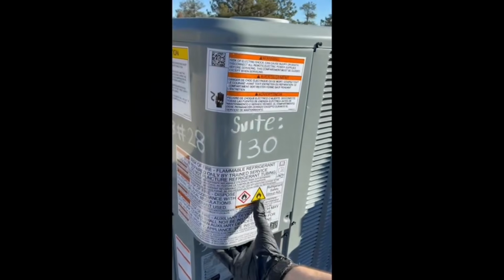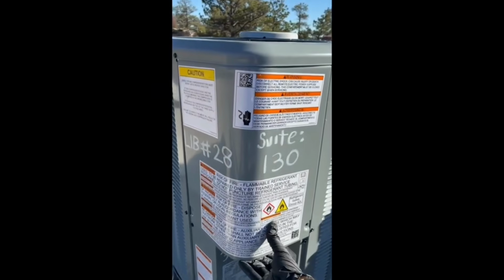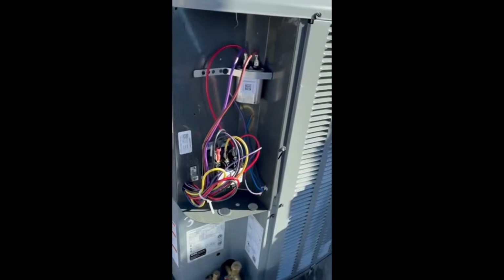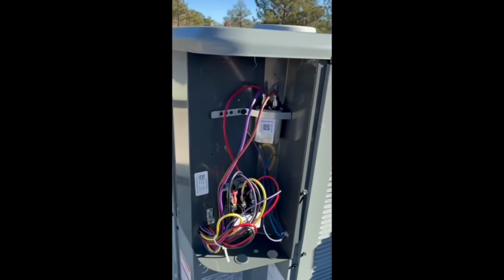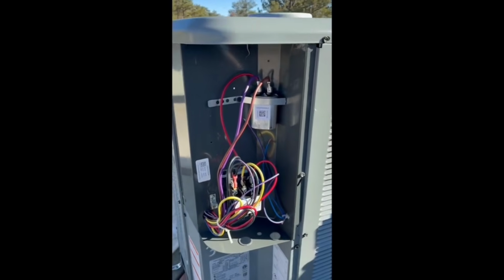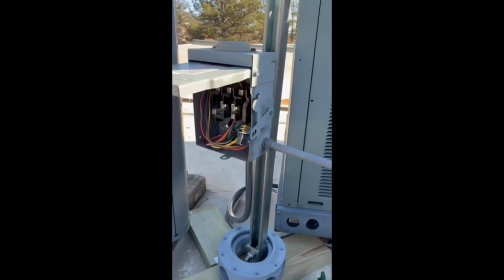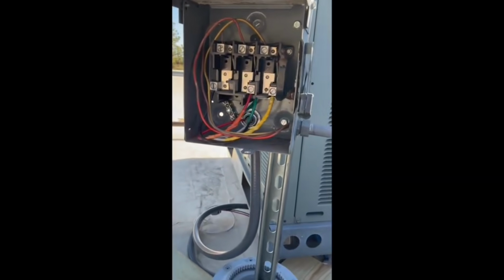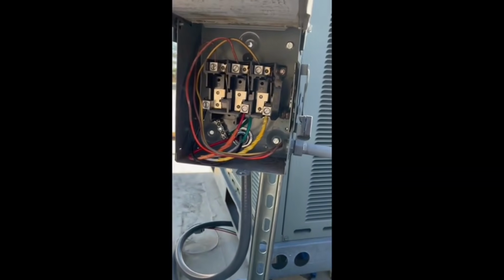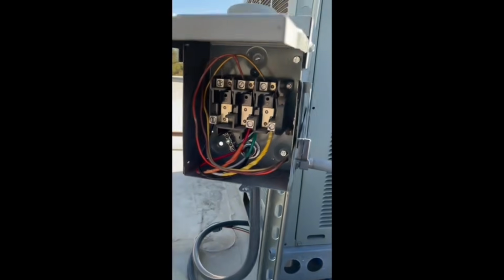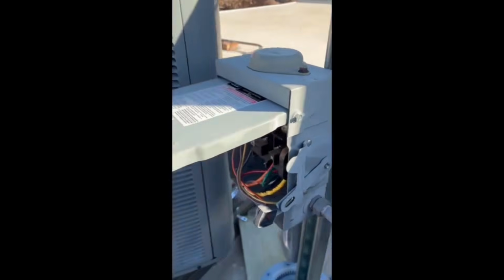Here's a new unit. We'll take this side cover off. There's our capacitor or contactor. So we'll bring in our wires. Here's a wiring schematic. This is a three-phase condensing unit. So there's the disconnect switch mounted. We've got our hot wires hooked up. Again, the power is still off. Now we just need to hook up the wires to the condenser itself.